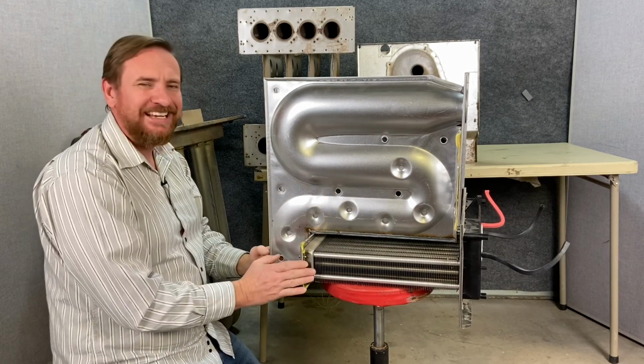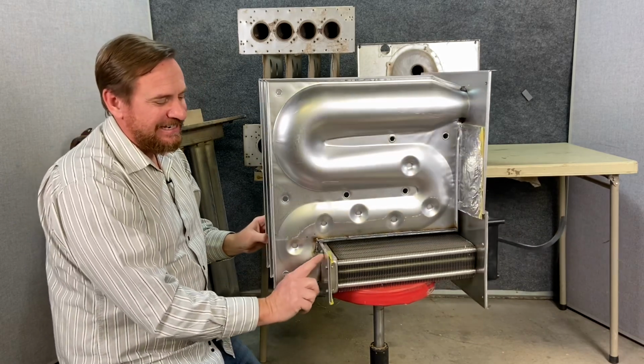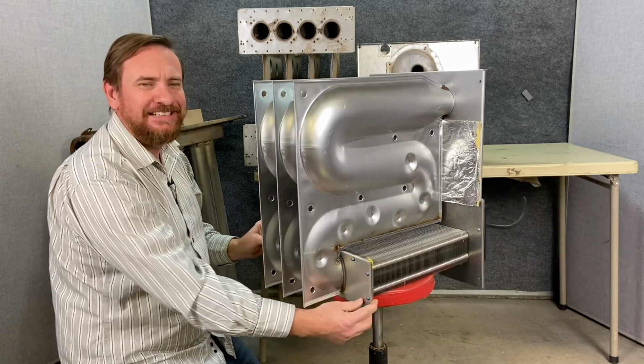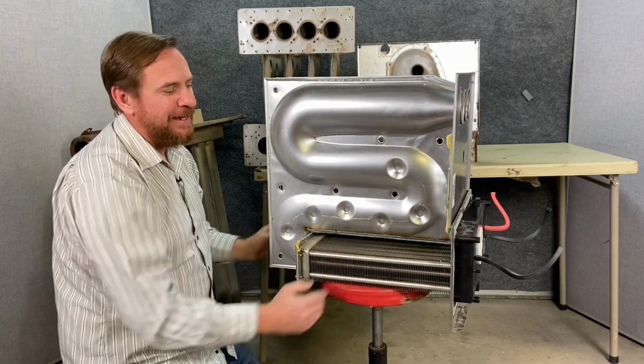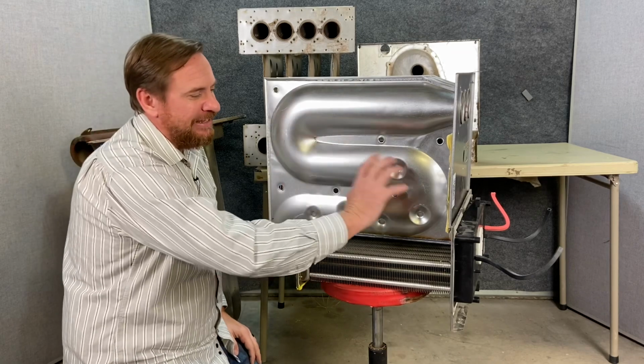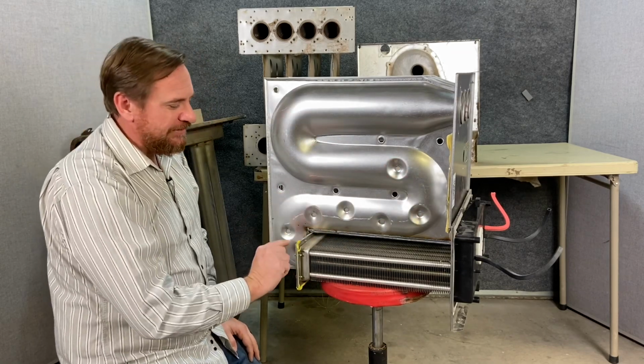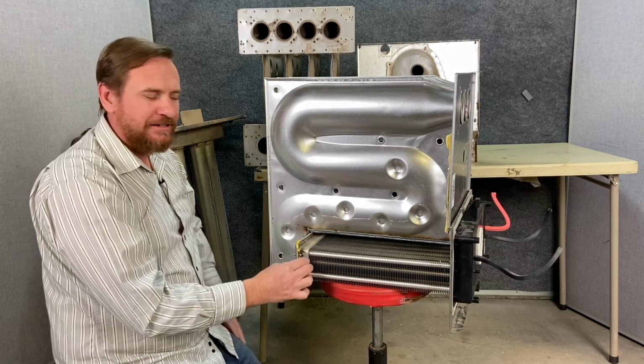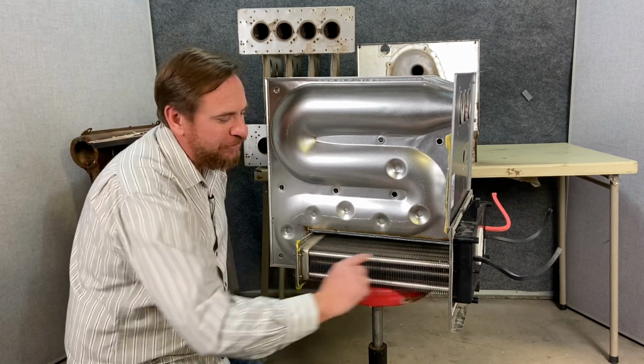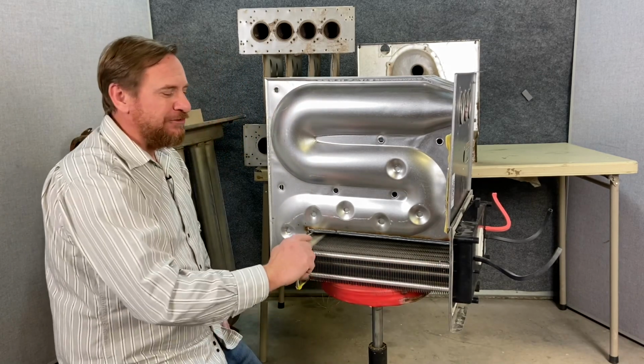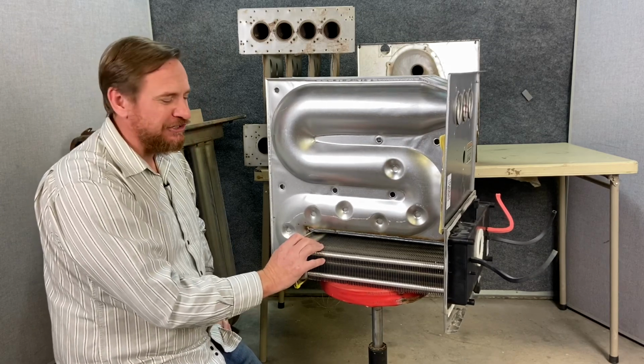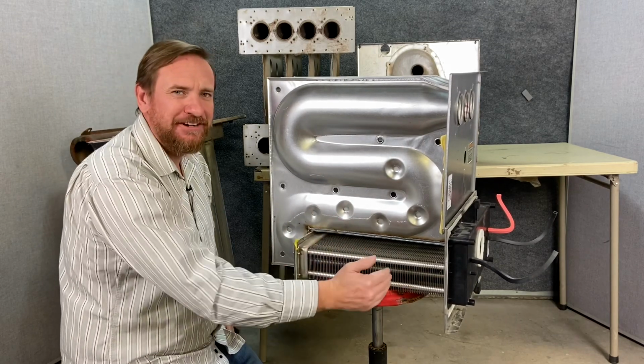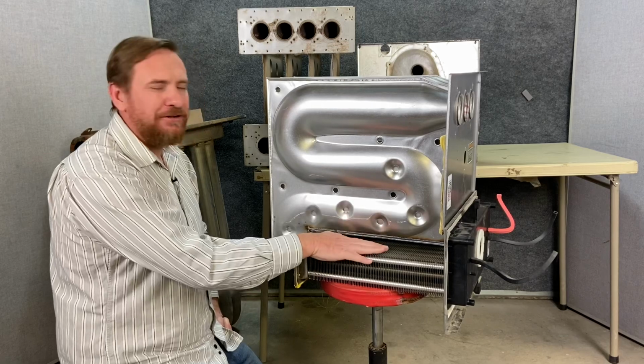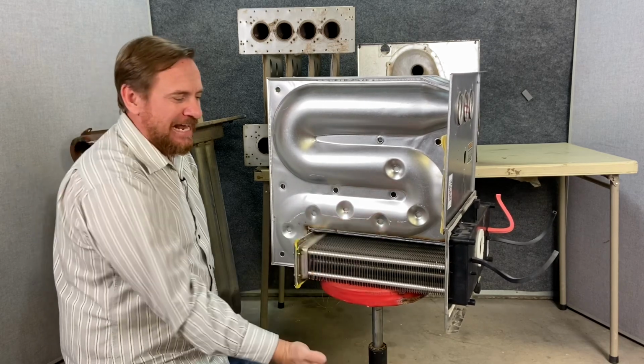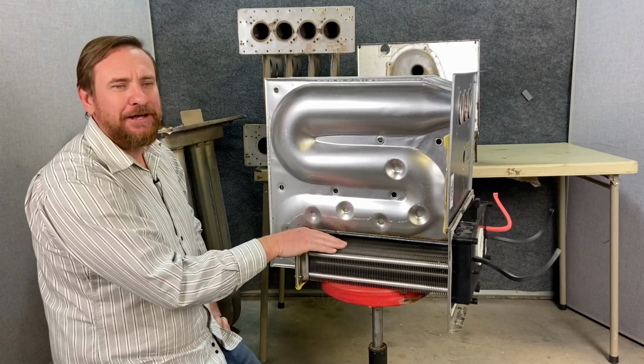We get down to the secondary heat exchanger. And the secondary heat exchanger is made of really nice stainless steel and looks very similar to an evaporator coil. So as we pull all the heat out of these hot gases, we then separate it into this collection box and we have these little bitty tubes running across. These little bitty tubes transfer heat even more efficiently. And then we have these fins on top of here. So there's a lot of metal touching a lot of the gases. And then on the outside, there's a lot of air touching a lot of the metal.